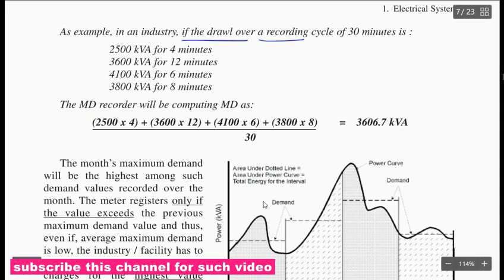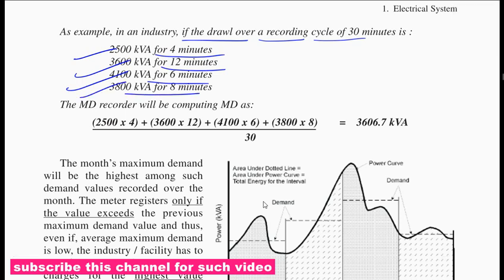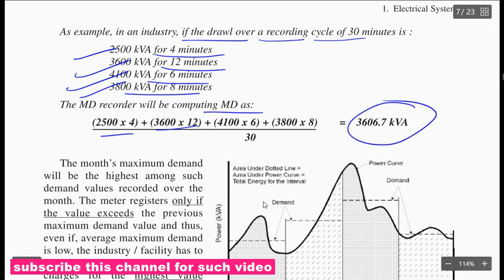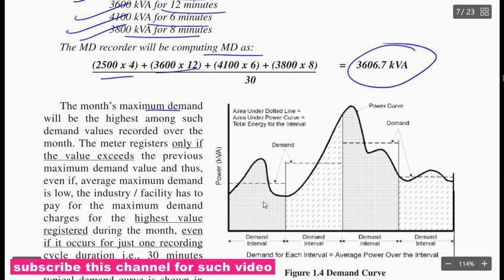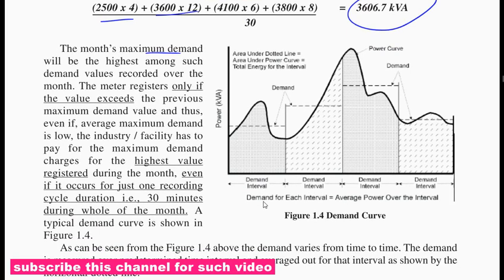It is drawn over a recording cycle of 30 minutes: 2500 kVA for 4 minutes, 3600 kVA for 12 minutes, 4100 kVA for 6 minutes, 3800 kVA for 8 minutes. The MD recorder will be computing MD as 2500 x 4, 3600 x 12, and so on, that is 3606.7 kVA. The month maximum demand will be the highest among such demand values recorded over the month.